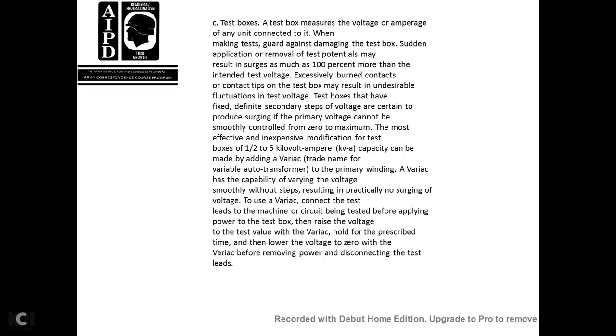C, test boxes. A test box measures the voltage and amperage of any unit connected to it. When making the test, guard against damaging the test box; Sudden application or removal of test potentials may result in surges as much as 100 percent more than the intended test voltage. Excessively burned contacts or contact tips on the test box may result in an undesirable fluctuation in test voltage. Some test boxes have fixed, definite secondary steps of voltage, producing surging, if the primary voltage cannot be smoothly controlled from 0 to the maximum.